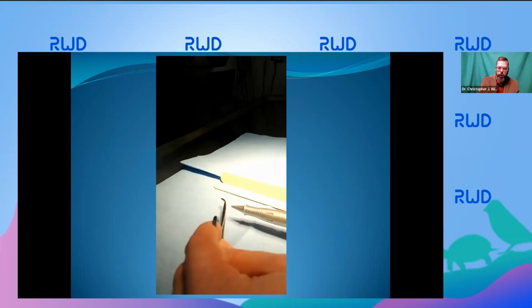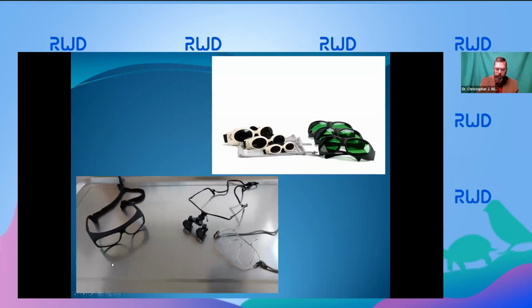Please protect your eyes with wraparound lenses. The optical density or OD number for each different laser wavelength will be printed right on the frames. CO2 laser safety glasses come as goggles, which can be worn over glasses, or inserts which can fit behind your own glasses. Prescription eyeglasses are typically not wraparound and will not protect you adequately from stray reflected rays.